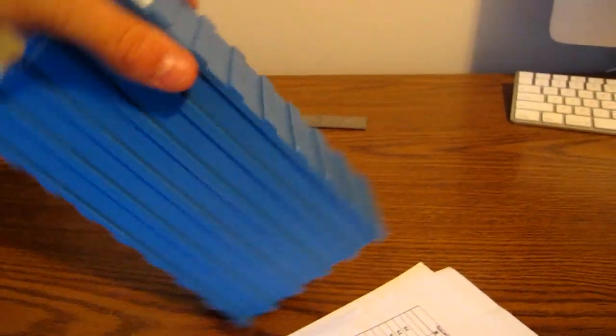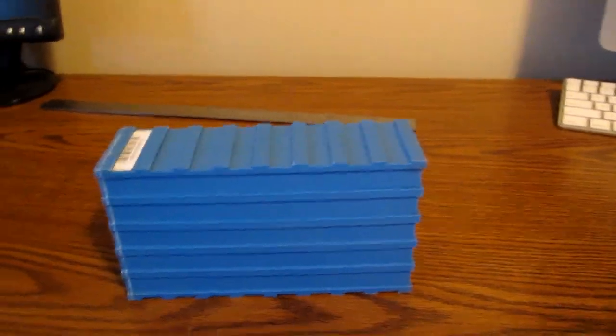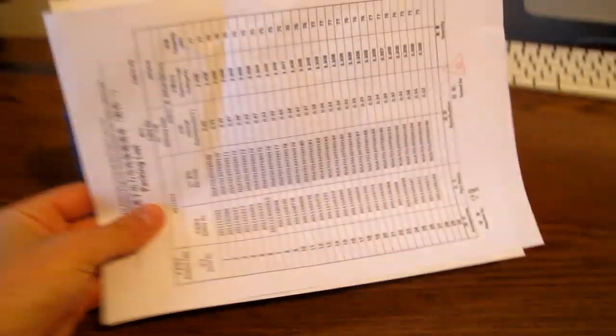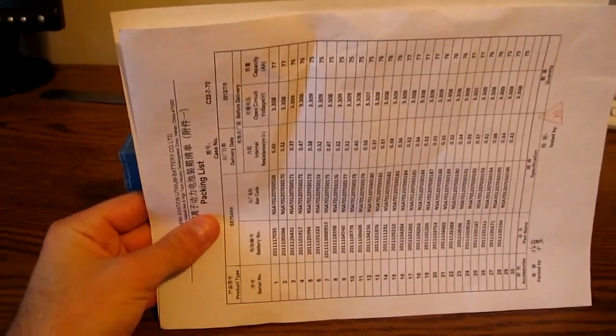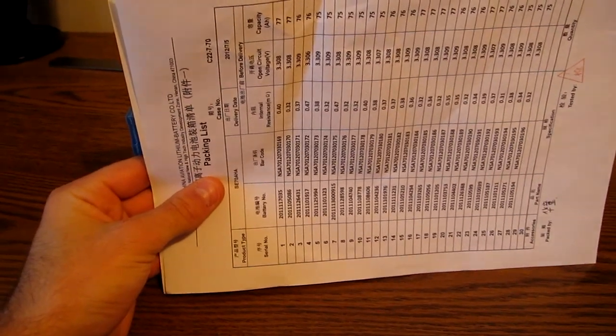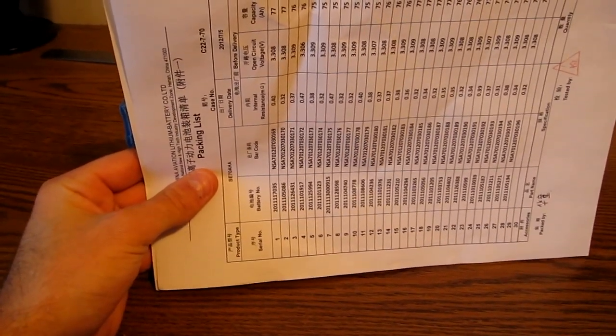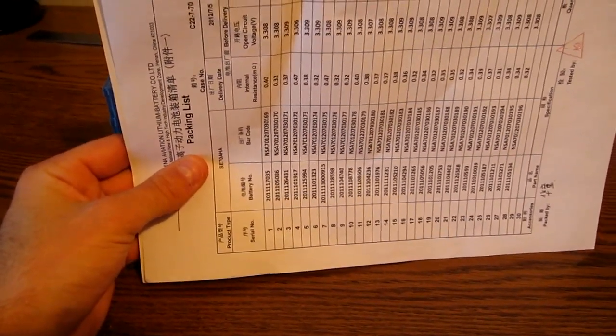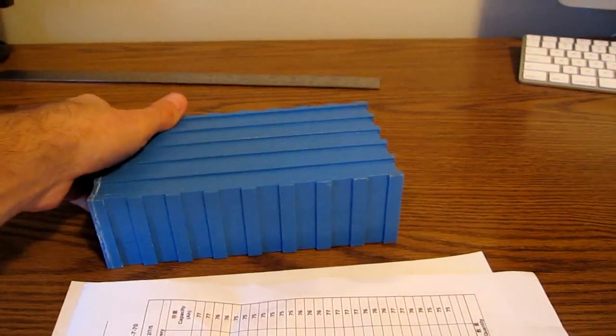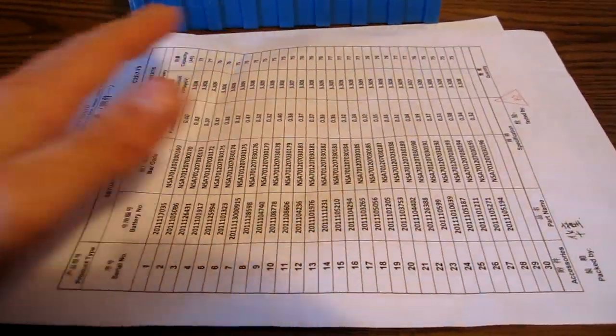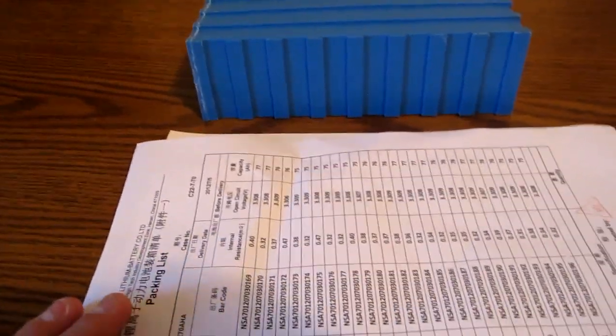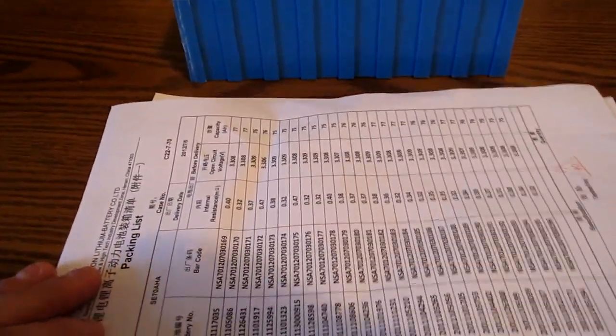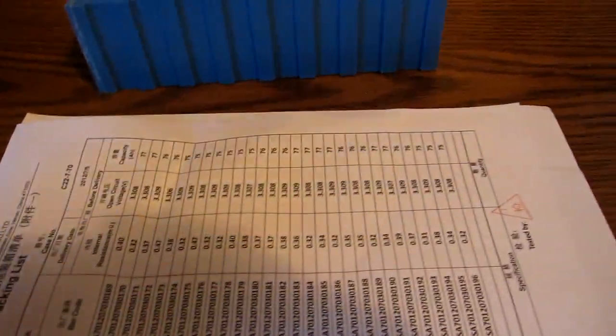If you were to tilt them this way like this with the cell on its side, the plates are now like this, you're still going to have equal distribution of the electrolyte all over the plates. But if you were to lay it flat like this, then over time gravity is going to pull the electrolyte from the top here down to the bottom. So you're going to end up with more electrolyte on the bottom sheet than you would on the top sheet and that's going to cause problems with the cell. That could cause internal resistance problems and capacity problems as well.